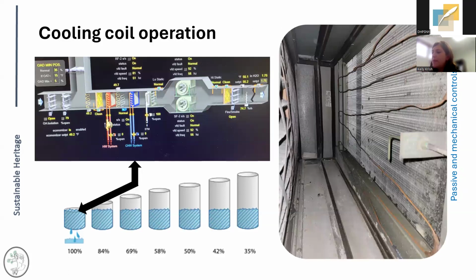Okay, so if you look at the image up here, this is a screenshot of what the software that controls an HVAC system can look like. If you talk to facilities, this is probably what they will look at to be able to tell what your cooling coil is achieving. Often they're labeled CC, or in this case, an abbreviation for chilled water, and blue, but that component with the arrow pointing towards it, that's our cooling coil.